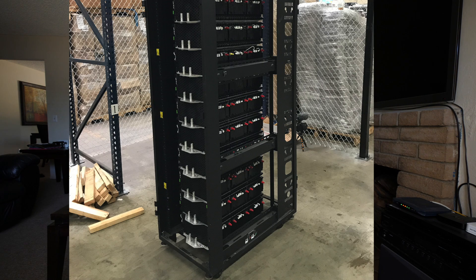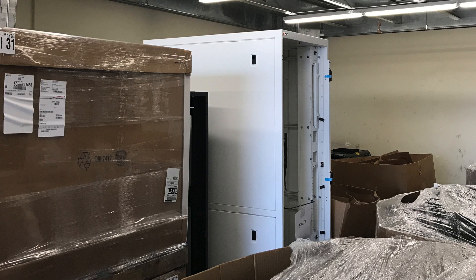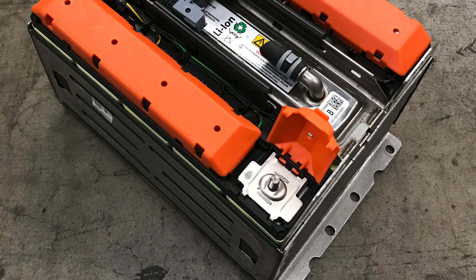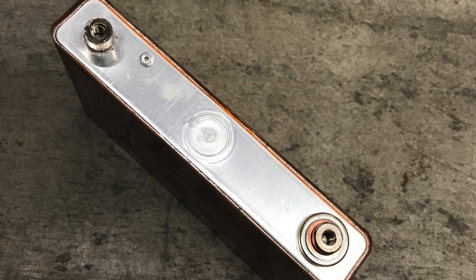Each one of these bricks yields about 2.6 kilowatt hours, so to get 100 kilowatt hours you'll need about 40 of them. The idea is to place these inside server racks, which are designed to hold sensitive equipment and have enough room — and frankly they look very similar to the white boxes that Tesla houses their batteries in. There are also two other types of batteries we'll be using: ones made by Bosch, and another type I haven't fully tested yet. All three types of cells will be housed in server racks and form part of the one megawatt power pack we're building in Chatsworth, California.